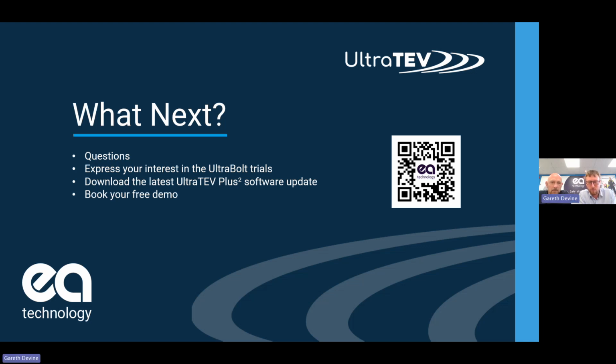So the first one: can I join the UltraBolt trial? Absolutely. We'll come back to you on that one. The second question is around the +2 and its use on the different asset groups. If you are doing a single survey or going out to site, yes, you can structure it so that before you go to site, you can define what measurements to take. And in one guided survey, that can include a piece of switchgear, a transformer, an outdoor section line, if you wish, all in the same file. So all of those results can be collected in one file and centralised as one recording, which is a change to previous. Yes.